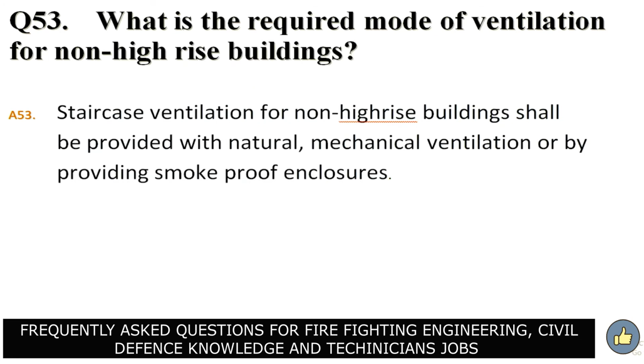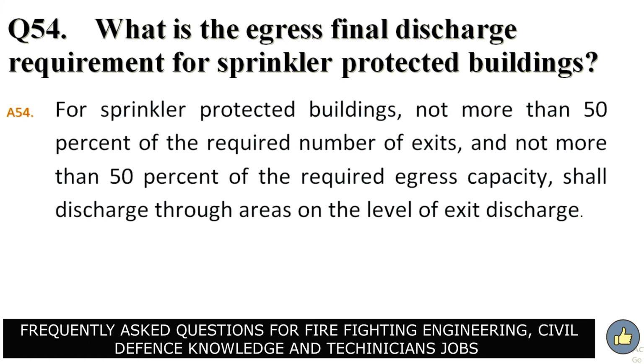What is the required mode of ventilation for non-high-rise buildings? Answer. Staircase ventilation for non-high-rise buildings shall be provided with natural or mechanical ventilation or by providing smoke-proof enclosures. What is the egress final discharge requirement for sprinkler-protected buildings? Answer. For sprinkler-protected buildings, not more than 50% of the required number of exits and not more than 50% of the required egress capacity shall discharge through areas on the level of exit discharge.